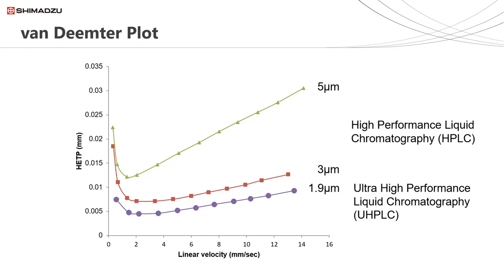This is an example of three Van Deemter plots for columns of different particle sizes. The top curve is for a column packed with five micron particles — notice how quickly plate height increases as mobile phase velocity increases. The middle curve is for a column packed with three micron particles and the bottom curve is for a column packed with 1.9 micron particles. Notice how increasing the mobile phase velocity beyond the optimal for minimum plate height does not have the dramatic detrimental effect on plate height as seen for five micron particles. The efficiencies seen for 3 and 5 micron particles are typically referred to as HPLC, and those seen for 1.9 micron particles or smaller as UHPLC or ultra high performance liquid chromatography.